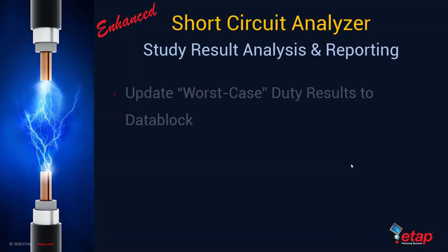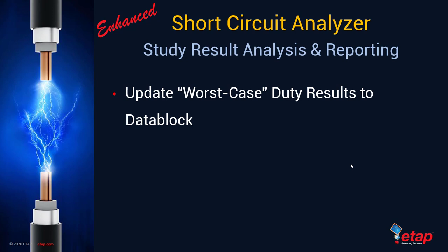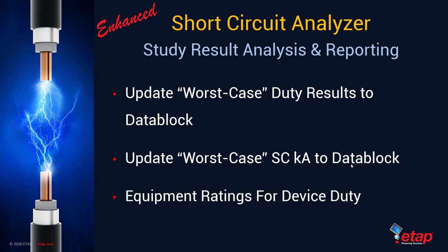Next is the short circuit analyzer, which has a massive improvement in the way we analyze study results and report them in a tabulated fashion. It now includes the ability to update the worst case duty results to the data block, meaning you can compute all your short circuit cases, let the short circuit analyzer compute the worst case condition, apply it to the data block, and print your one-line diagram. You can also include equipment ratings for device duty against which you are comparing the short circuit results.